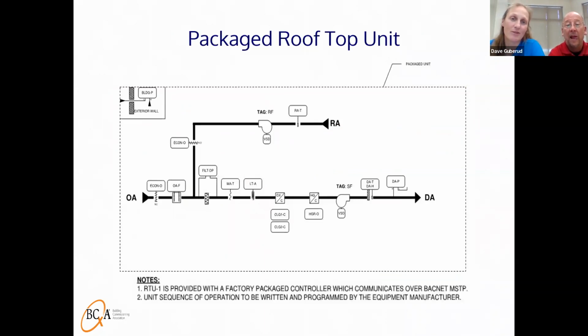So here we have a package rooftop unit, and this is the schematic that was created. Number 2 down there in the notes is actually a really nice note. So this is the 1%. I think I said before that 99% of controls contractors seem to just copy and paste the sequences from the designer. Well, here's a 1%er. They put in the note that the unit sequence of operation is to be written and programmed by the equipment manufacturer. This is because it's a packaged unit with factory packaged controls, and they know that. So it was really nice to see them take that step.